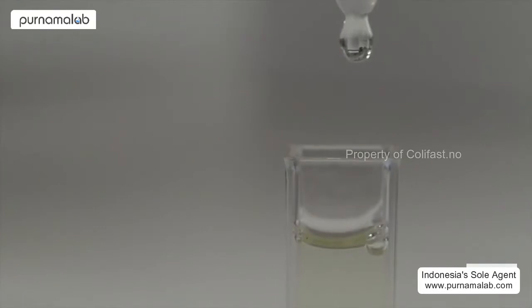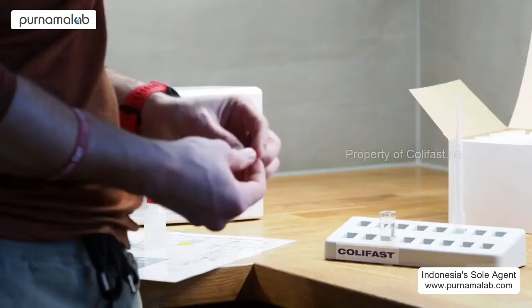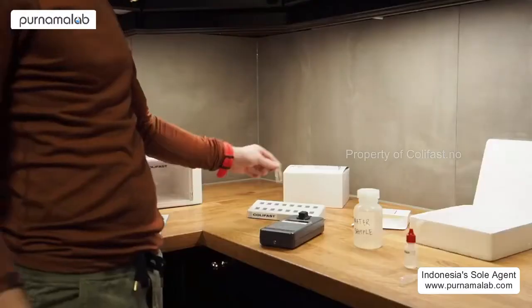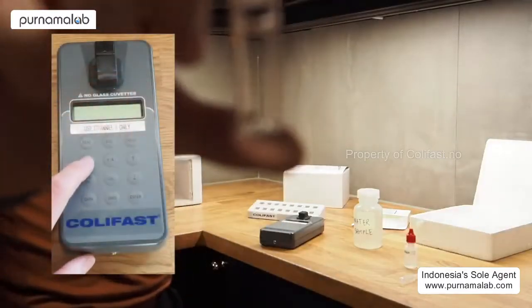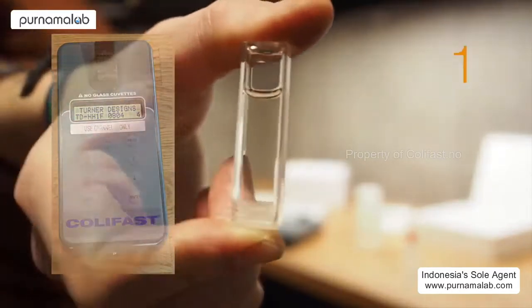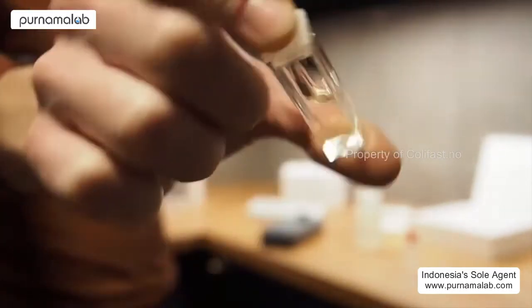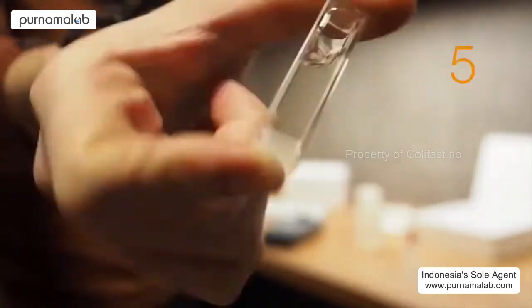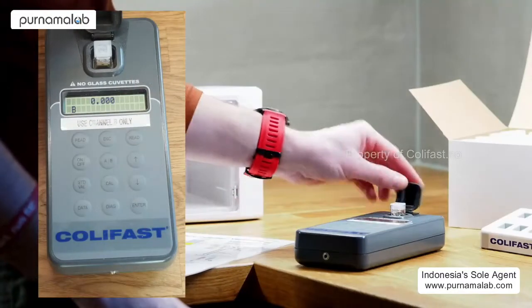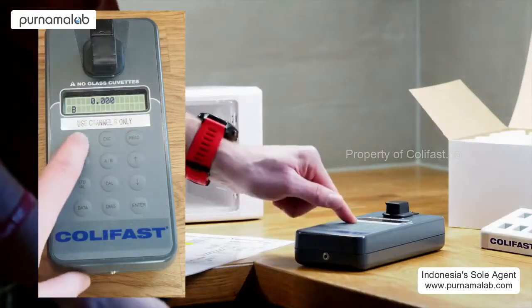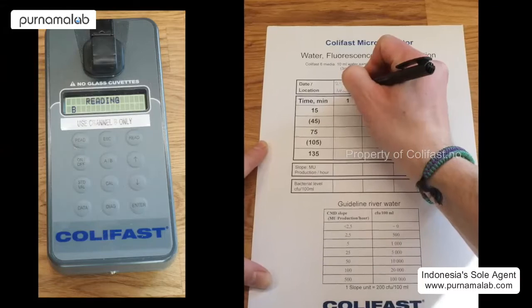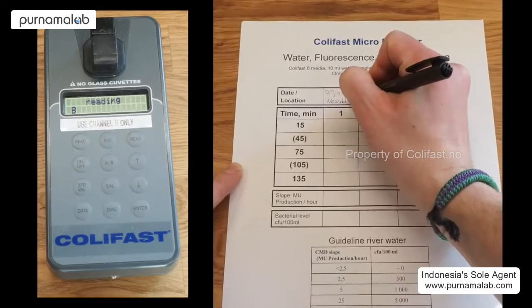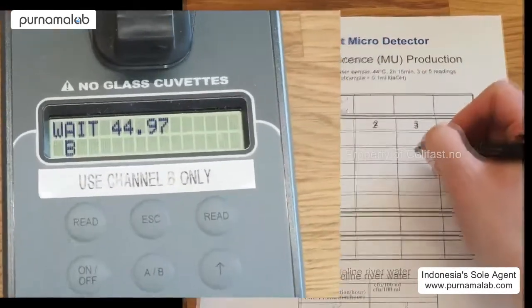Before the measurement can be carried out, 3 drops of developer are added to the cuvette. The highly basic sodium hydroxide changes the pH of the solution, enhancing the fluorescence of the fluorophore, methyl umbelliferone. The cuvette is inverted several times before being put in the fluorometer. Be careful to do the adding of the sodium hydroxide, inverting of the cuvette, and the reading immediately after one another. No pause in between.